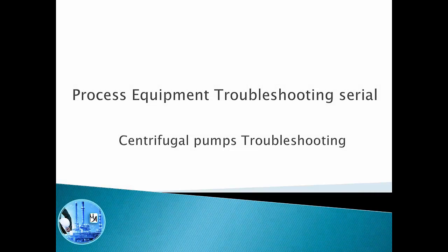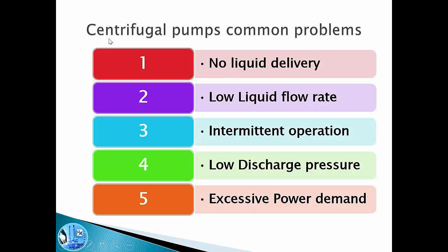Welcome everyone. In this process equipment troubleshooting series, today I will talk about centrifugal pump troubleshooting. Usually in the industry there are five major common problems for centrifugal pumps: the pump is not giving any liquid delivery, the pump is giving low liquid flow rate, the pump is having intermittent operation, the pump is giving low discharge pressure, or there is excessive power demand.